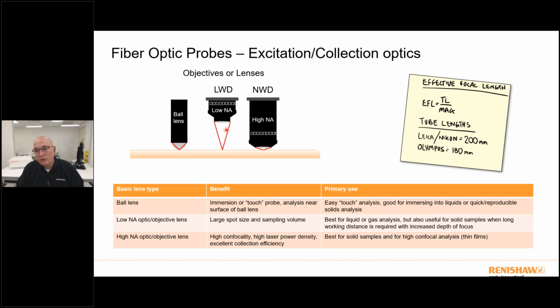If you were trying to do something inside a deposition chamber or at high temperatures, then maybe that's not necessarily what you want. Maybe you need some long working distance so you can stare through windows and get down to wherever your experiment is taking place. So those long working distance optics generally have lower numerical aperture lenses, and these can still be microscope objective lenses. But then you're still concerned about your analytical spot size.